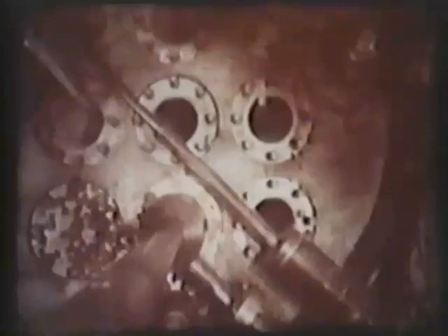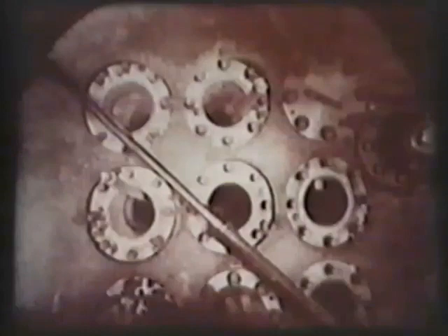Films taken of the reactor head area showed that six nozzles were open to the atmosphere. Only one appeared to be completely free of obstruction. Films taken looking down through the nozzle openings revealed extensive damage to the visible part of the core and to the control rod shrouds. Control rod extensions still protruding up through the nozzles indicated that most of the control rod blades were still in the core region. The central rod blade appeared to be ejected from the core.